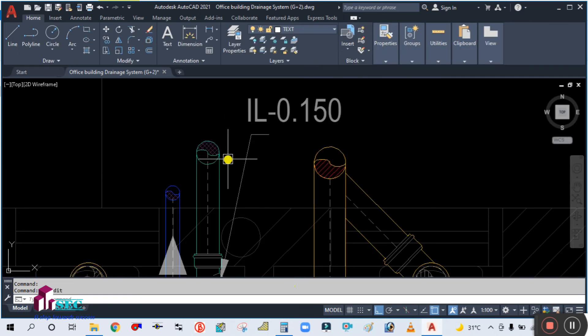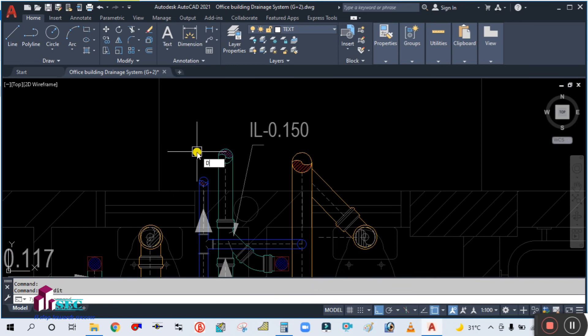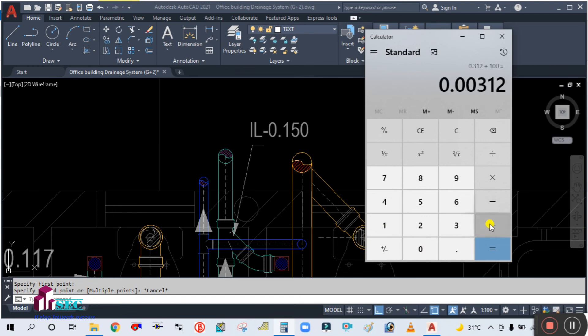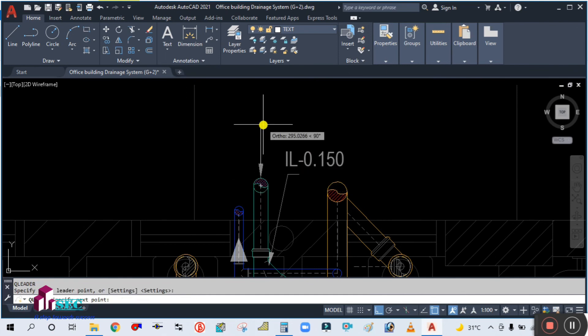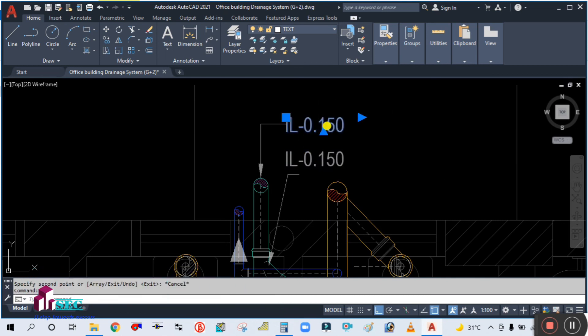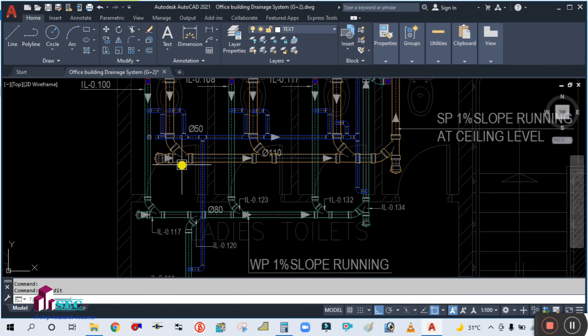Similarly, what will be the invert level at this riser fitting? Check the distance from this point to this point — it is showing 312 mm. So 312 divided by 1000, then divided by 100 gives 0.003. Add 0.003 plus 0.150, so 0.153. Here your invert level will be 0.153. Simply copy this and place it here, double-click to edit, and write 0.153.